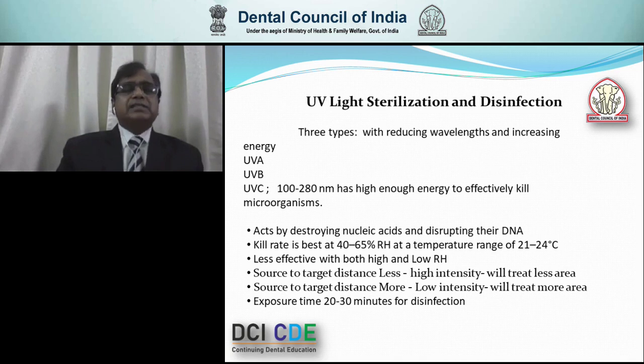UV-C light is the one used for UV light sterilization and disinfection. It has a wavelength of 100 to 280 nanometers, and it is effective in killing microorganisms by destroying nucleic acids and disrupting their DNA. The kill rate is best at 40 to 65% relative humidity. This is very important if you are going to buy a UV light sterilizer. The temperature range should also be between 21 and 24 degrees for the best effectiveness.